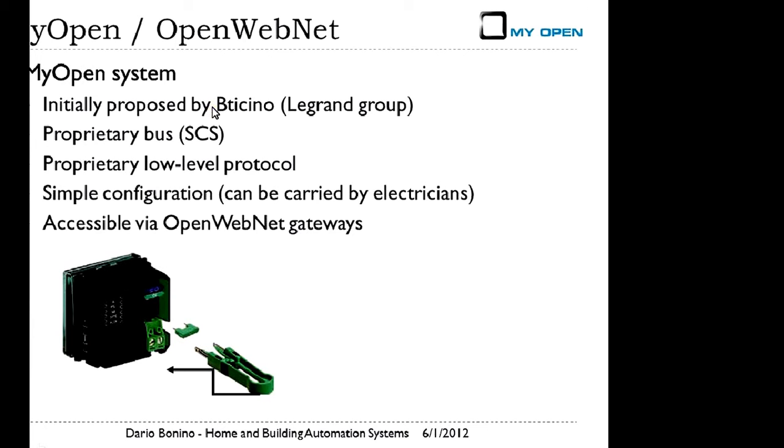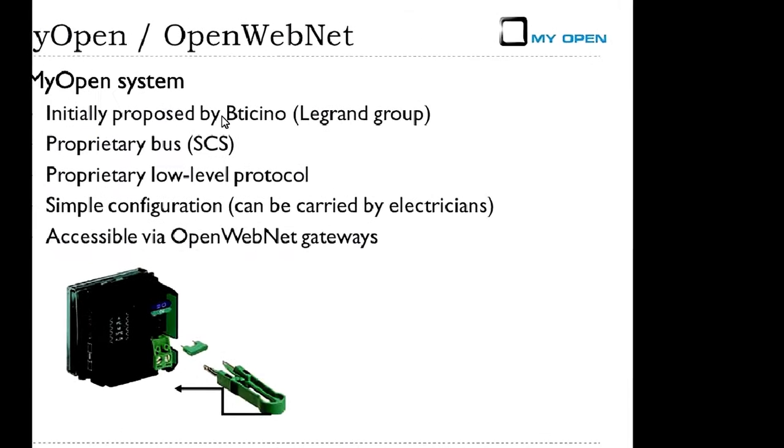And the big design choice that they made some years ago is to keep the bus closed, but to open the protocol to access the bus. So even if the communication on the bus is closed, so we don't know anything about the low-level communication on the wire, what we know is the protocol to speak with the gateways from this technology, so we can interact with the devices on the bus.